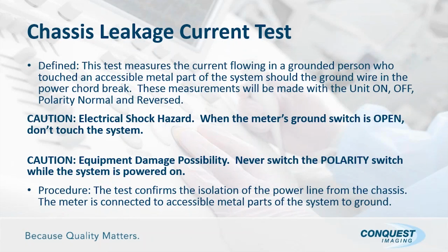There is a possibility of equipment damage, especially if you're using an automated meter or safety analyzer, because some of them don't have program stops allowing you to shut the system down prior to changing polarity, and when you change polarity it will kill power to the system and you'll shut the system down hard. So make sure that prior to changing polarity you do manually shut the system down.